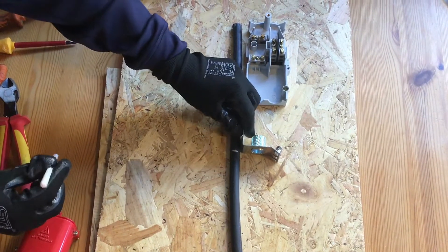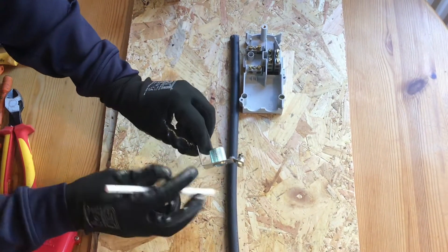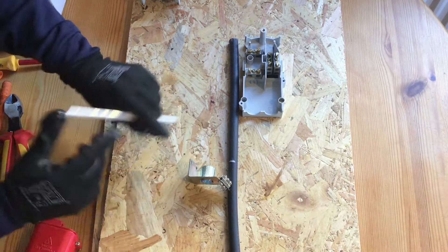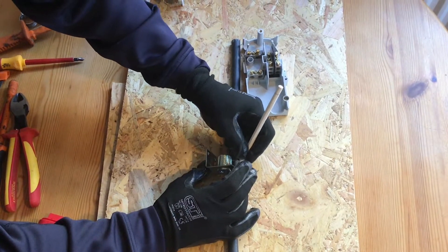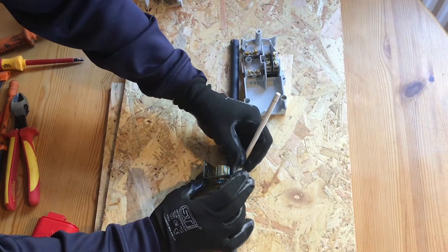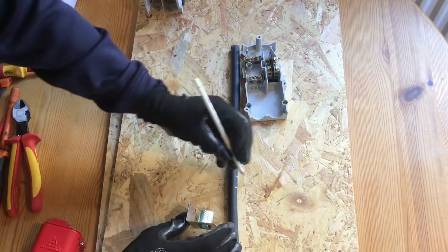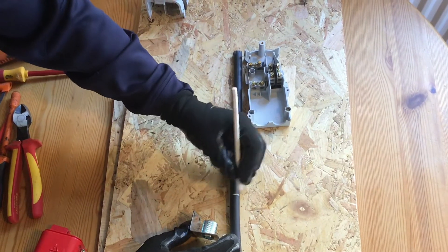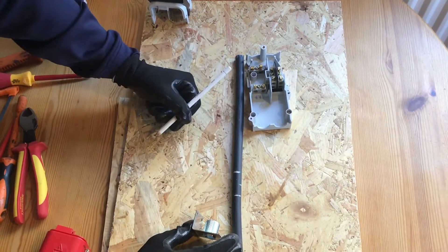The idea is the armours will eventually pass through this hole here and fold back on themselves down to here. In which case, I'm now going to go one, two times this length back — and here is where I will strip the PVC and here is where I'll make my cut for the armours.